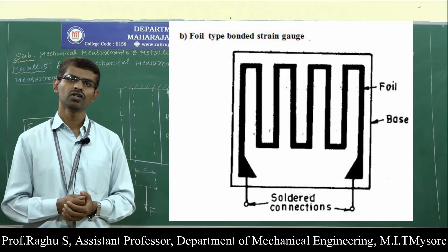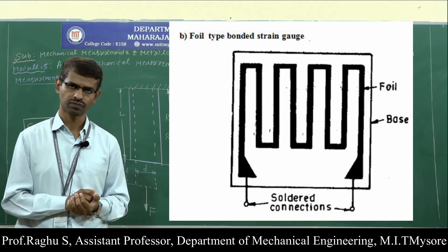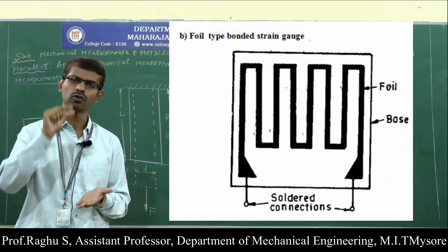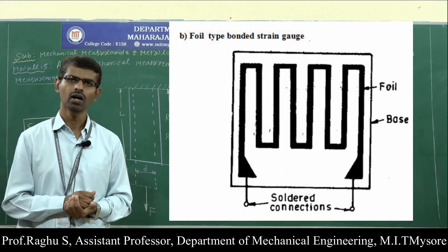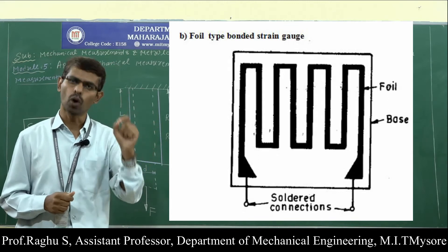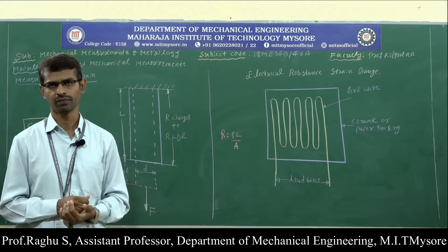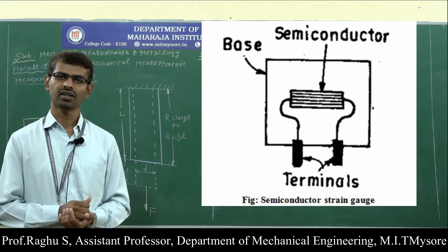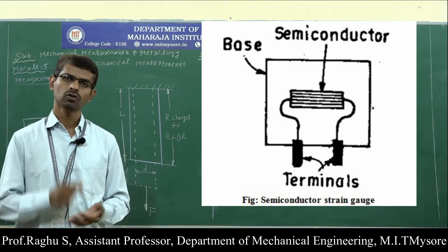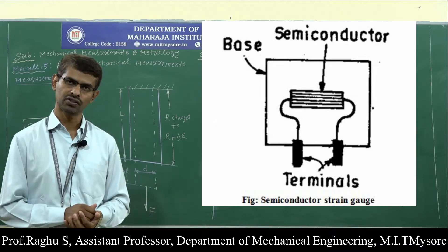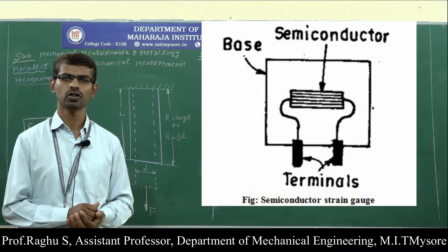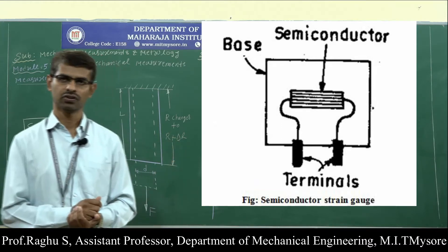The foil type strain gauge has a metal foil arranged in a zigzag manner, supported by backing material which may be thin paper or plastic. The assembled strain gauge is bonded or pasted to the structure whose strain has to be measured. The semiconductor strain gauge consists of a rectangular filament made from semiconductor material, supported by stainless steel or plastic backing material. Leads are provided for electrically connecting the strain gauge to the Wheatstone bridge.